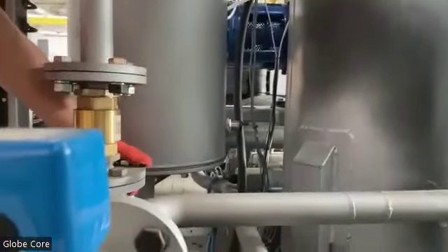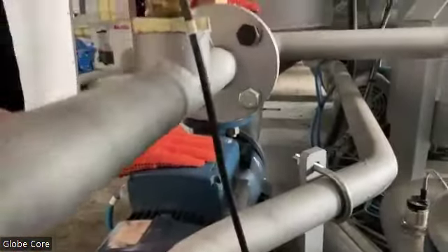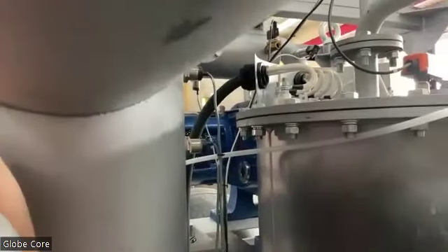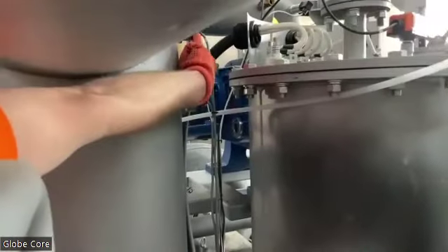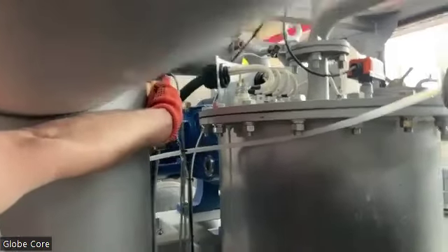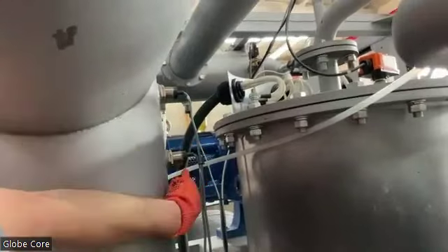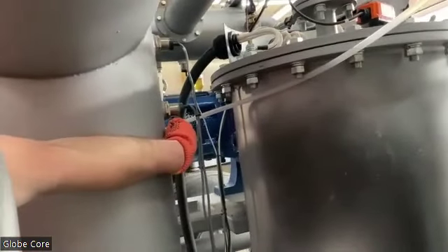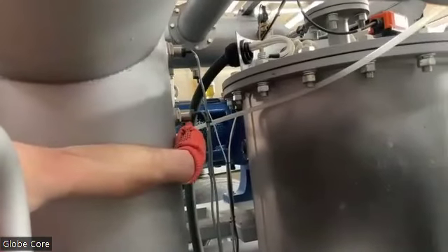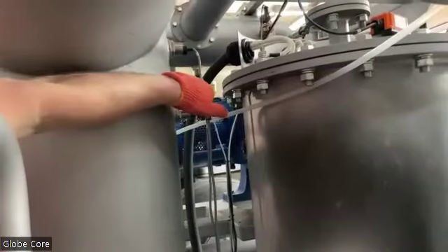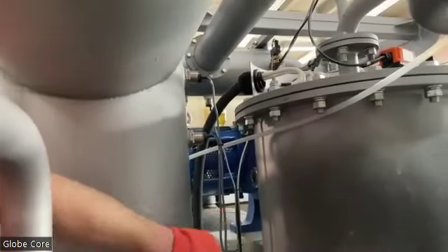If no oil is detected by the bottom level sensor of the vacuum chamber, the outlet pump cannot run. Then we have 2 sensors on the top, and they control operation of the inlet pump. So if oil is detected by the top sensor, it stops the inlet pump, and the inlet pump starts again when the oil level drops down to this middle sensor. If the level goes lower than this sensor, the inlet pump starts again.